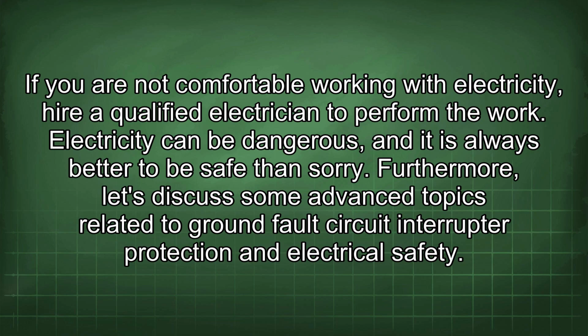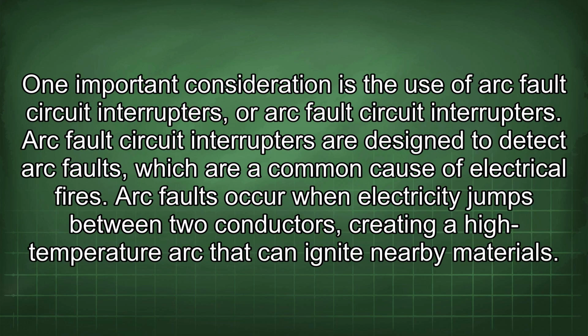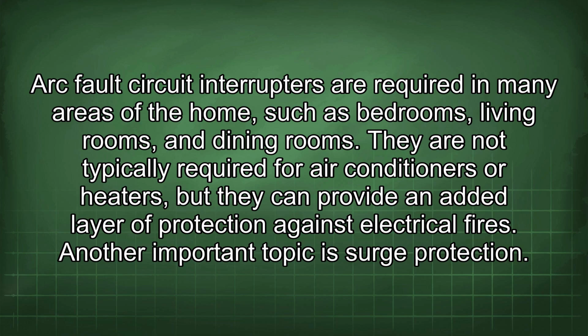Furthermore, let's discuss some advanced topics related to ground fault circuit interrupter protection and electrical safety. One important consideration is the use of arc fault circuit interrupters. Arc fault circuit interrupters are designed to detect arc faults, which are a common cause of electrical fires. Arc faults occur when electricity jumps between two conductors, creating a high-temperature arc that can ignite nearby materials. Arc fault circuit interrupters are required in many areas of the home, such as bedrooms, living rooms, and dining rooms.